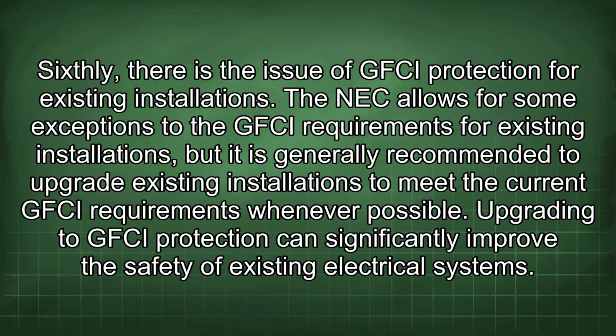Sixthly, there is the issue of GFCI protection for existing installations. The NEC allows for some exceptions to the GFCI requirements for existing installations, but it is generally recommended to upgrade existing installations to meet the current GFCI requirements whenever possible. Upgrading to GFCI protection can significantly improve the safety of existing electrical systems.